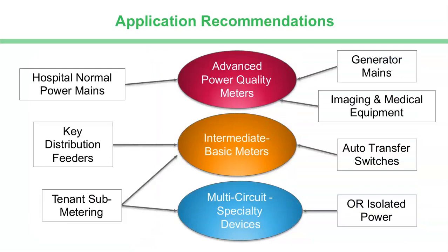Here's how I recommend they're applied. So your advanced power quality metering in a hospital setting, in my view, should always be utilized for hospital normal power mains and for generator mains. That's where power quality starts, is at the source. And if that power quality is poor, all of your loads are going to suffer. So it's very important. If you have vulnerability, existing conditions, or there's concern for your imaging and medical equipment, it can also become a very wise choice to incorporate the advanced metering on those circuits as well.